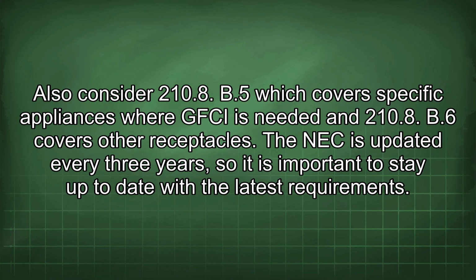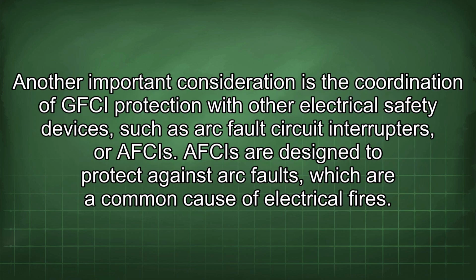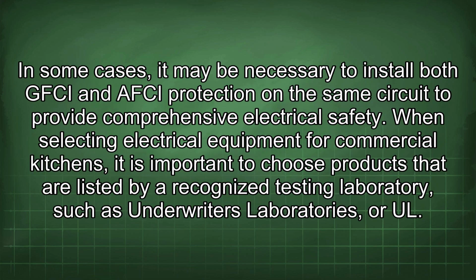Another important consideration is the coordination of GFCI protection with other electrical safety devices, such as arc fault circuit interrupters, or AFCIs. AFCIs are designed to protect against arc faults, which are a common cause of electrical fires. In some cases, it may be necessary to install both GFCI and AFCI protection on the same circuit to provide comprehensive electrical safety.